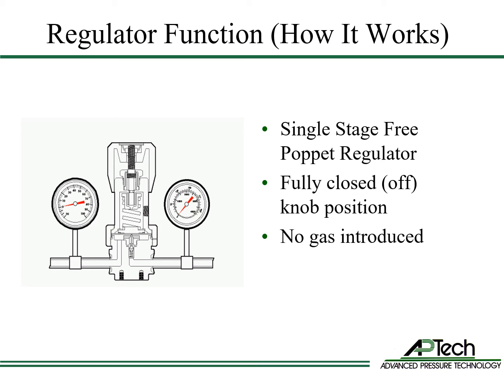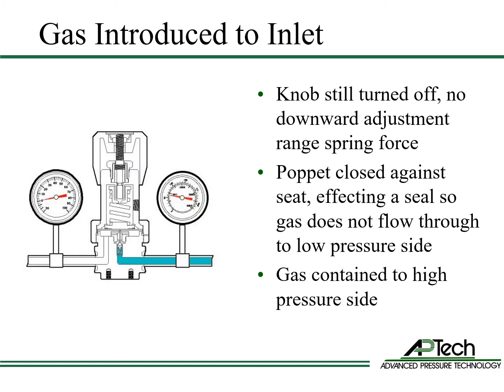The regulator is in the fully closed position with the knob turned counter-clockwise until it stops. There is no gas introduced in the system. Now gas is introduced to the high pressure side of the regulator. The knob is still turned off, so the diaphragm spring is not applying spring force onto the diaphragm. The poppet is closed against the seat, effecting a seal. Gas does not flow through to the low pressure side. Gas is contained to the high pressure side.